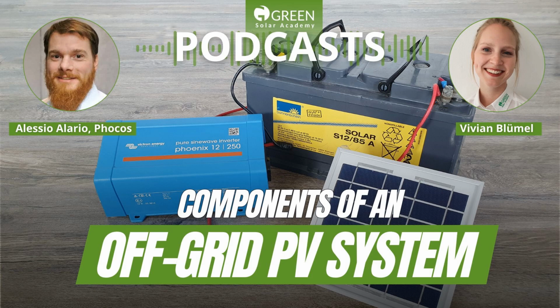Yeah, so like I said, the PWM is essentially just a glorified light switch. So let's say you have a high PV voltage of, let's say 30 volts, and you have a battery of 12 volts. Then a PWM charge controller will just connect your PV modules to your battery and then disconnect it again if necessary, many thousand times a second. And essentially, if you look at the voltage of your PV modules, it will be 30 volts, then 12 volts, 30 volts, 12 volts, etc. There's nothing in between. And an MPPT charge controller can work in between that. And that's really where all of the advantages come from.